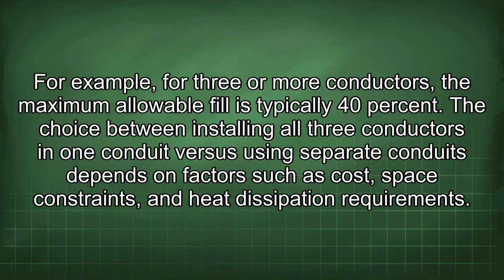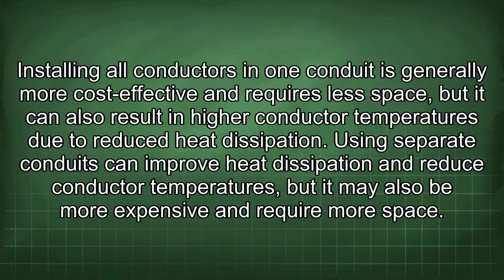The choice between installing all 3 conductors in one conduit versus using separate conduits depends on factors such as cost, space constraints, and heat dissipation requirements. Installing all conductors in one conduit is generally more cost-effective and requires less space, but it can also result in higher conductor temperatures due to reduced heat dissipation. Using separate conduits can improve heat dissipation and reduce conductor temperatures, but it may also be more expensive and require more space.